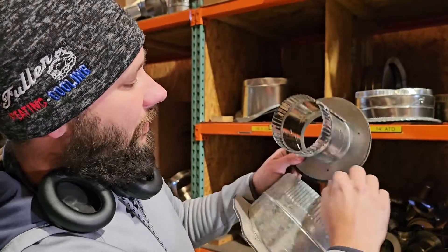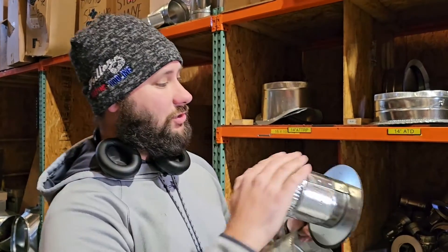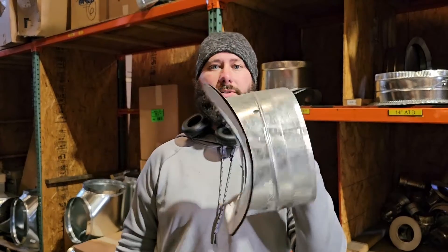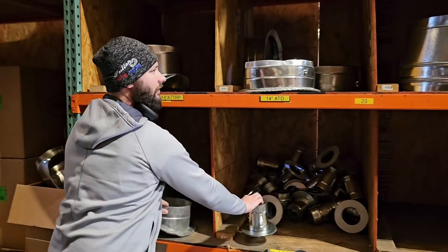It's already got some pre-drilled holes so you can screw it into the trunk. Then you want to actually seal this. You can use some duct mastic or you can use some Polyken mastic tape. So I just want to show you the difference between a flat takeoff and a round takeoff so you know the difference. We've got a bunch of fittings here and I'll go ahead and show you some more.